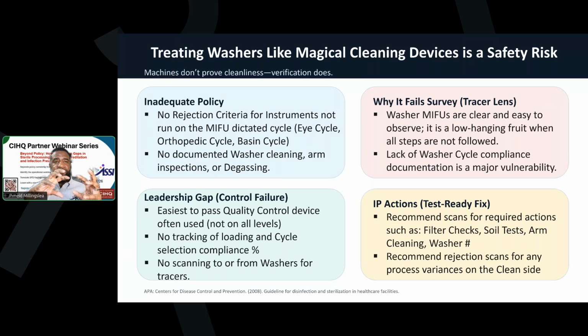One of the other things is that the IFUs for the washers tell you that you have to clean a filter, and unfortunately you have to screw those arms off. When you do that and dump it out, you're going to find tip protectors and chemical indicators, or you have to do it weekly, every 3 days. Some of them don't say you have to degas, right? And if the policy doesn't say to do that, then guess what? The team is going to be so operationally focused that they're going to miss that step. And you don't want that. You want to help them get it.